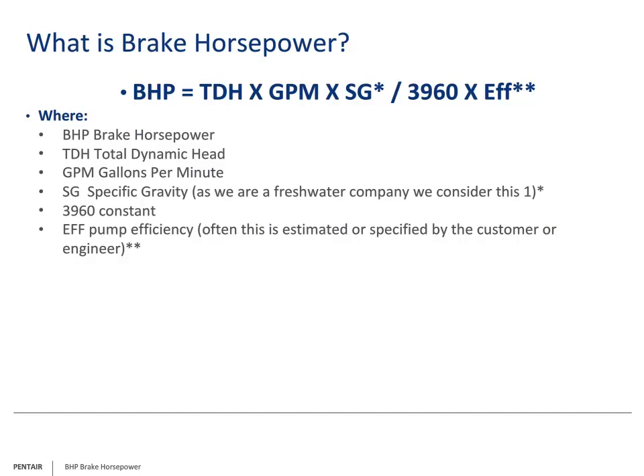What is brake horsepower? Simply put, it is the horsepower needed at the system requirements. To calculate the horsepower needed, you need to know the system total dynamic head, or TDH, the gallons per minute of the system, and the specific gravity of the product being pumped. In our industry we essentially ignore this, as we are pumping water with a specific gravity of one.